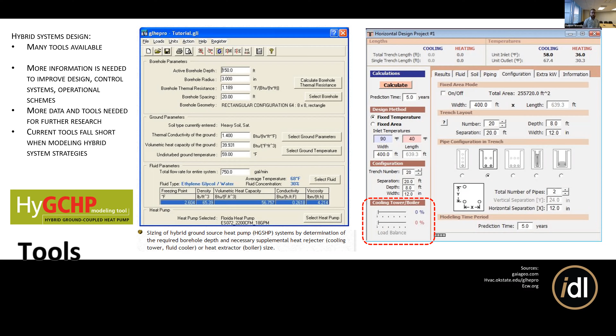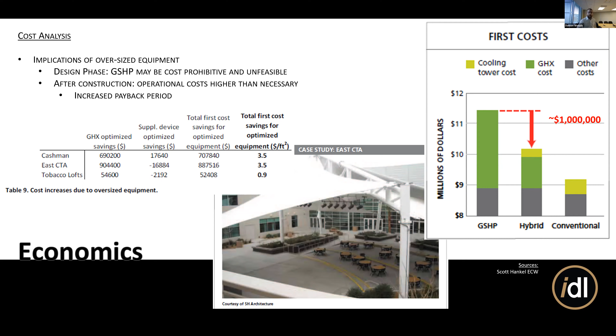Let's talk about the heart of the matter: economics, because these systems are not going to get installed if there's not a payback. A hybrid system can significantly reduce first costs, even adding in the supplemental equipment. This was one case study from the Energy Center of Wisconsin. Adding a cooling tower did increase the cost a little bit, but they downsized their ground loops so much that, in terms of millions of dollars, they saved pretty significantly. By reducing their total first costs, that saved them in the long term on their payback.